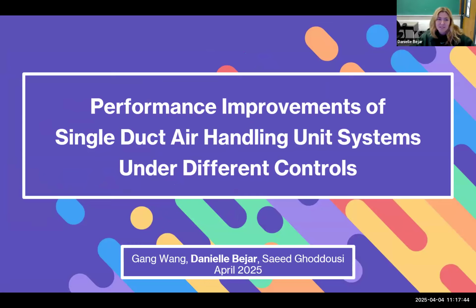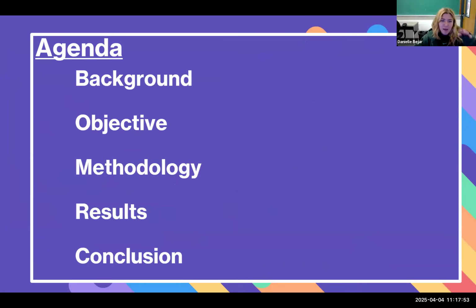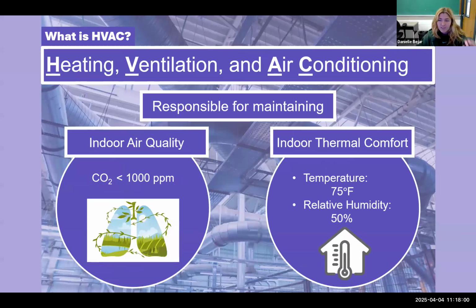Hi, everyone. I'm Danielle. I'm going to be talking about performance improvements of single duct air handling unit systems under different controls. So I'm going to go through some background, state the objective, go through methodology, show some results, and then we'll conclude. The system I'm going to be talking about is the HVAC system. HVAC stands for heating, ventilation, and air conditioning. And it's responsible for two things. Number one, maintaining indoor air quality at carbon dioxide levels less than 1,000 ppm. And the second responsibility is to maintain indoor thermal comfort, so making sure that the air inside of the building is at 75 degrees Fahrenheit and 50% relative humidity.